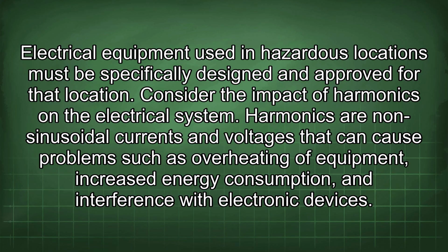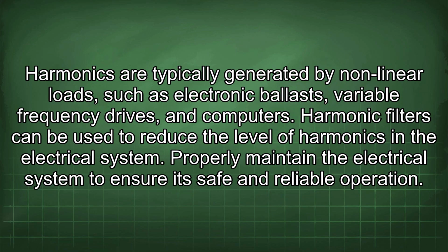Consider the impact of harmonics on the electrical system. Harmonics are non-sinusoidal currents and voltages that can cause problems such as overheating of equipment, increased energy consumption, and interference with electronic devices. Harmonics are typically generated by nonlinear loads such as electronic ballasts, variable frequency drives, and computers. Harmonic filters can be used to reduce the level of harmonics in the electrical system.